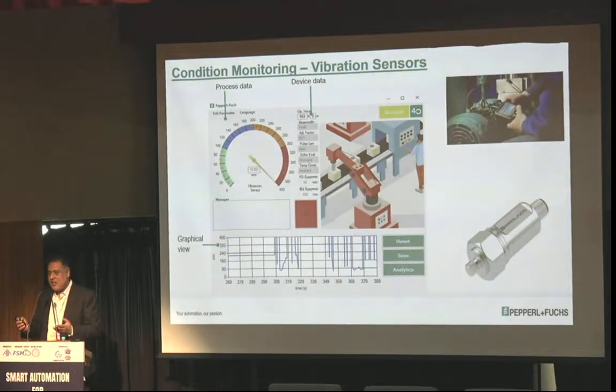Now, condition monitoring is also an important aspect. We need to check whether the machine is performing as per the requirement or not. Whether there is a vibration in the system, because of the vibration, there is wear and tear of the machine, and which causes a lot of downtime. So a normal vibration sensor can be connected, and you can have a dashboard where you can see the process values, where you can store the historical trends, and then retrieve it. And in case the vibration goes beyond a certain limit, it can be immediately captured, and the machine can be immediately stopped for the maintenance work. So vibration sensors, temperature sensors, flow sensors, all together can work for condition monitoring of a normal legacy machine.